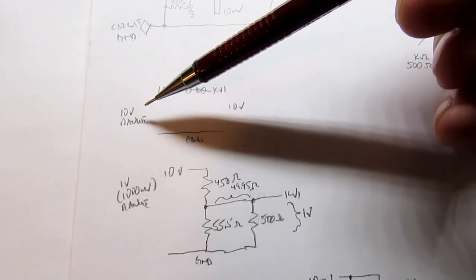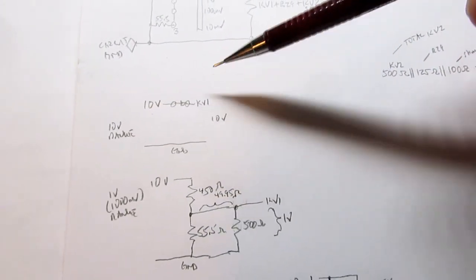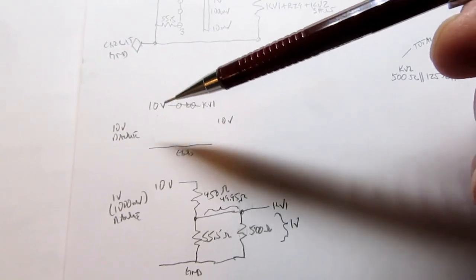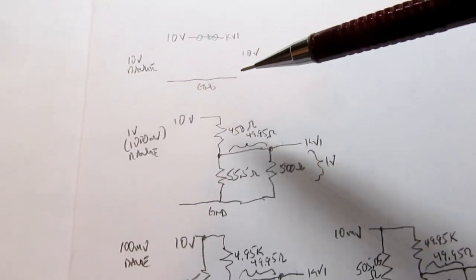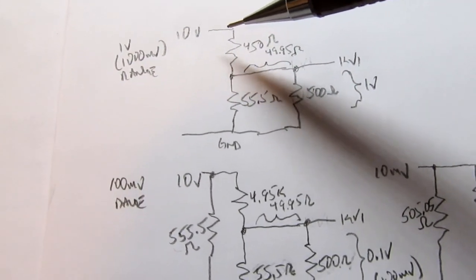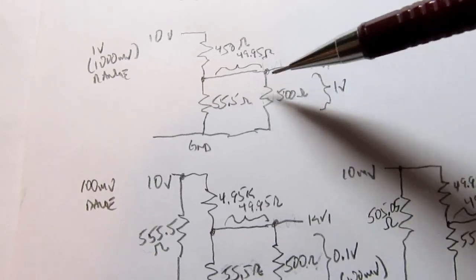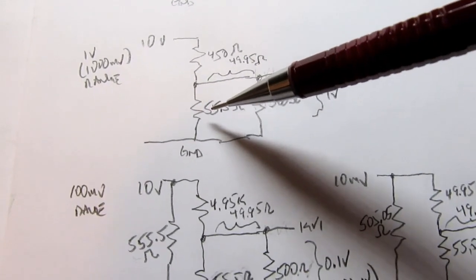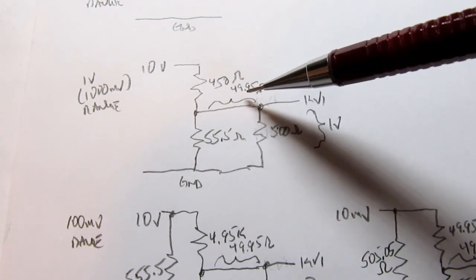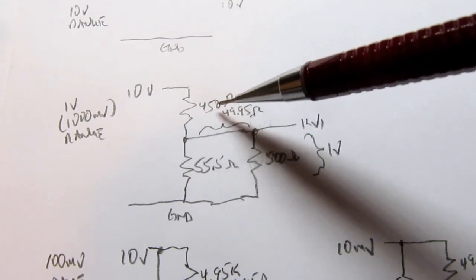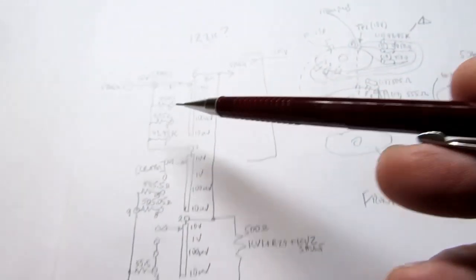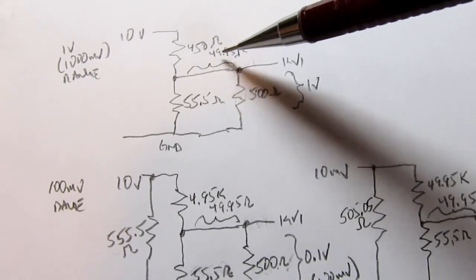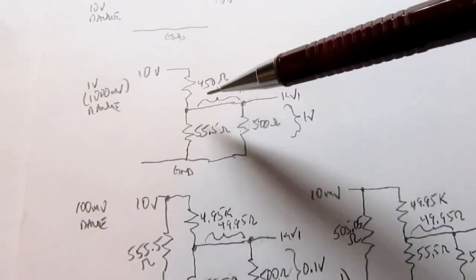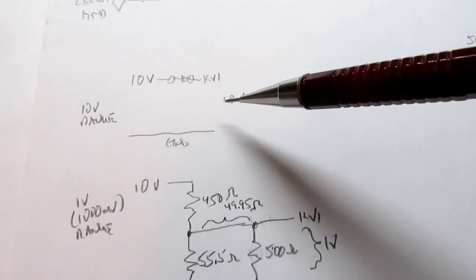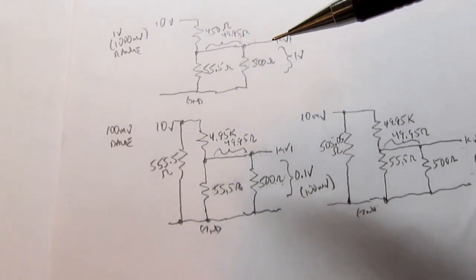If you're in the 10 volt range, then you have the 500 ohms of the Kelvin-Varley circuit as a load, so it's perfectly good with a 500 ohm load. If you go into the 1000 millivolt or 1 volt range, now you take the 500 ohms of the Kelvin-Varley circuit, but it's reduced by the 55.5 ohm resistor, so it's only about 50 ohms. You add that to a 450 ohm resistor introduced by the range switch, and guess what - 50 ohms plus 450 is 500 ohms. The regulator still sees the same 500 ohm load, just like it would appear when the Kelvin-Varley circuit is the only load on the voltage regulator.